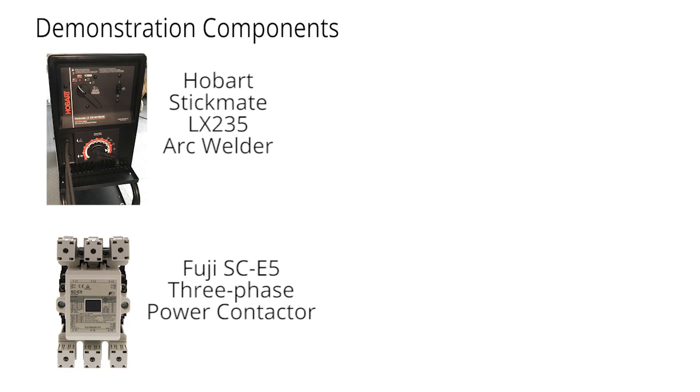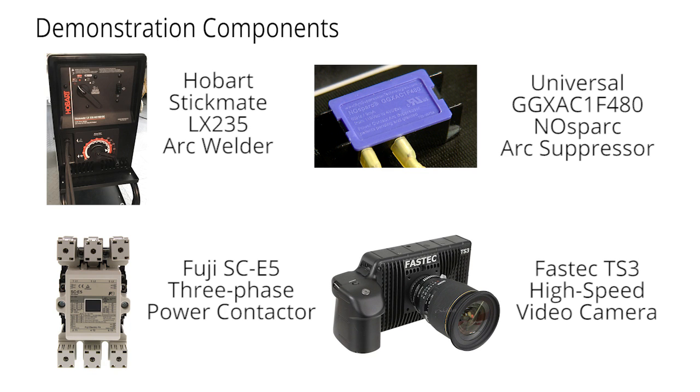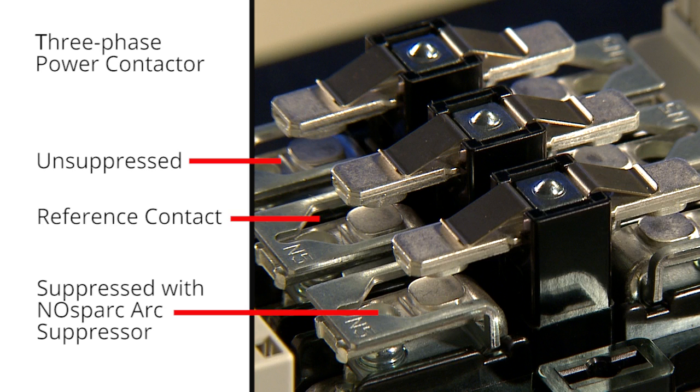Here's how we structured this demonstration, beginning with the following key components: one Hobart arc welder, one robust Fuji three-phase power contactor, one universal GGXAC1F480 NOsparc arc suppressor, and one Fastec TS3 high-speed video camera. Our demonstration plan called for using one leg of this contactor to demonstrate how NOsparc suppresses arcing energy, the opposite leg to demonstrate the destructive ability of unsuppressed arcing, and the middle leg to serve as a reference contact subjected only to mechanical forces with no current passing through.